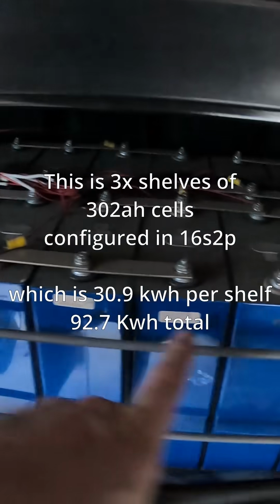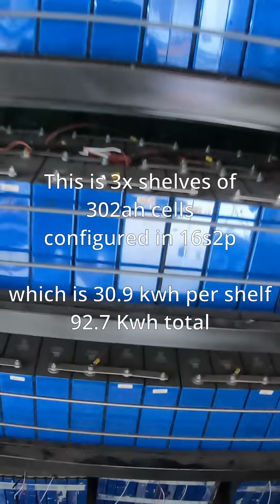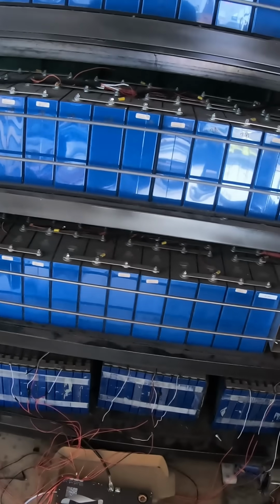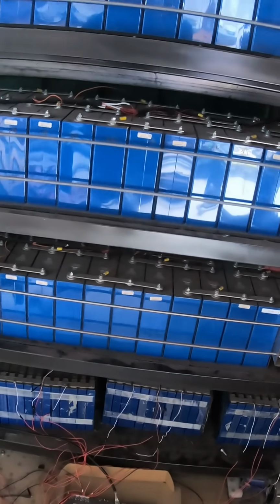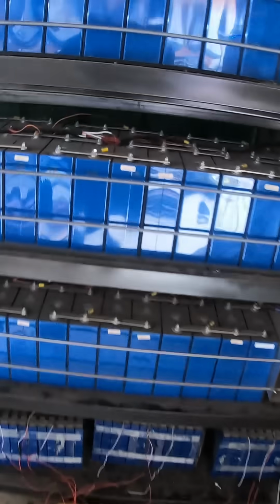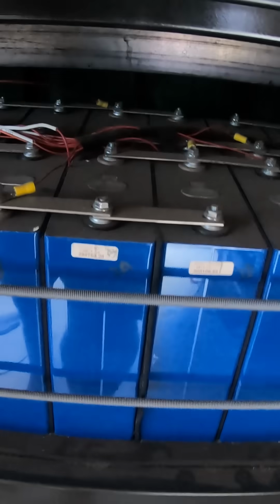So one of the criticisms that we get in this pack is that we've got a 2P configuration, and people say, well, you won't know if something's failing. Well, that's simply not true. It doesn't matter if they're a single 600 amp hour cell or two 300 amp hour cells, right?